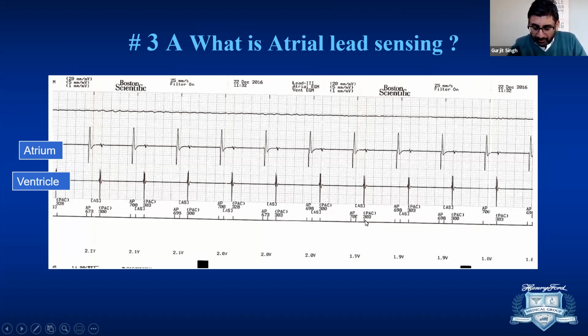So the third marker event is correct. That's a ventricular signal being sensed on the atrial channel. So that's a far field signal. So that is correct. But the question is, what is this middle thing? Okay. And if you look carefully on this ECG, as the pacing output is reduced, that middle signal goes away when you're at 1.8 volts.